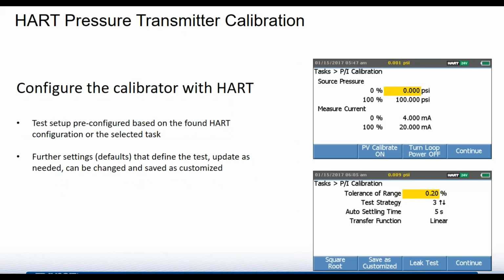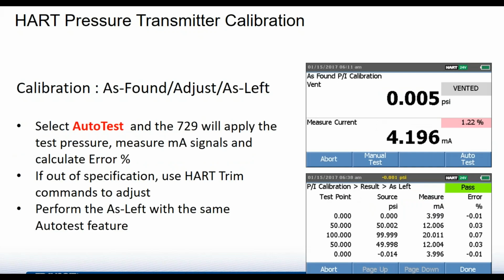So configuring is going to be pretty much the same as doing the configuration on a calibrator with the hand pump. It's going to automatically give you that information: what your source pressure needs to be, what your 4-20 output is. And again, if it's a downloaded task from software, you're going to have things like your tolerance and the test strategy already built in. If not, if you're doing a manual test, then you'll need to plug those values in.